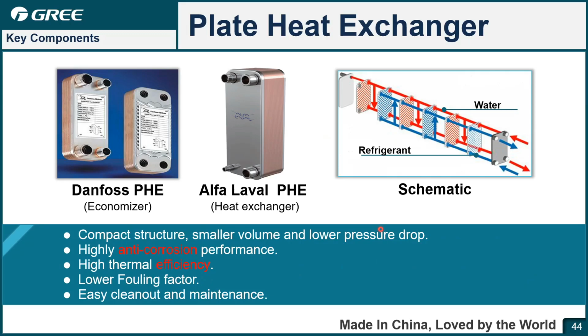For the plate heat exchanger, in the VERSATI 3 there are two PHE. The first one is the economizer, is a small size PHE. Another one is the major heat exchanger for hot water here. So actually, for this economizer, the heat exchange is between the refrigerant and the refrigerant. However, in this PHE, the heat exchange is between refrigerant and hot water. And also, you know, for this one, there's anti-corrosive material. Yeah, and also PHE, the efficiency is very high, and also the size is small, so that we can integrate PHE into the other units.